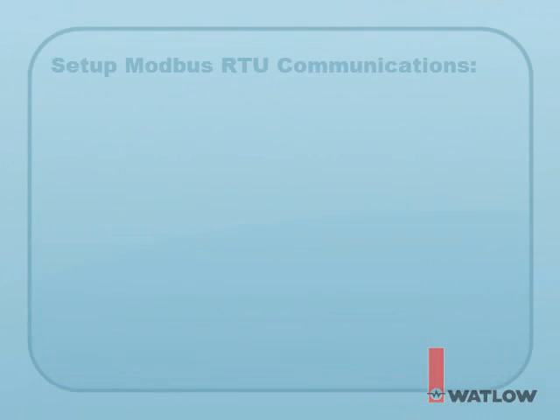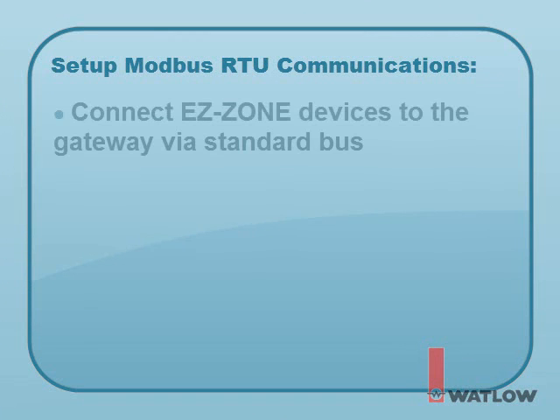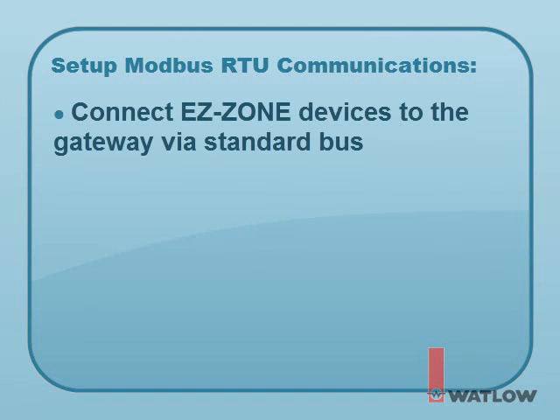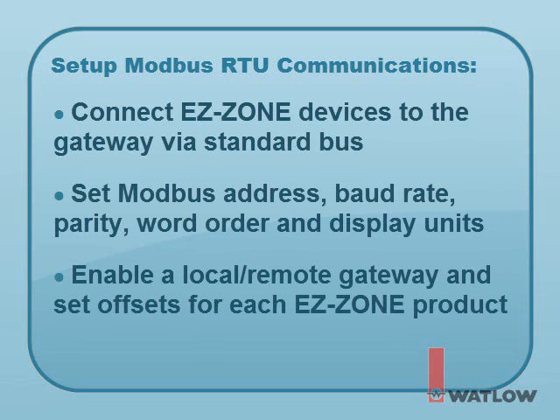To set up Modbus RTU communications between a Silver Series OIT and EZZone products through a gateway in an RUI or Access module, you must connect the EZZone devices to the RUI or Access module via standard bus. With EZZone configurator, set the Modbus RTU settings on the Gateway's Communications 2 menu, including the Modbus address, baud rate, parity, word order, and display units. And finally, enable a local remote gateway and set the offset for each EZZone product that will communicate through the gateway.